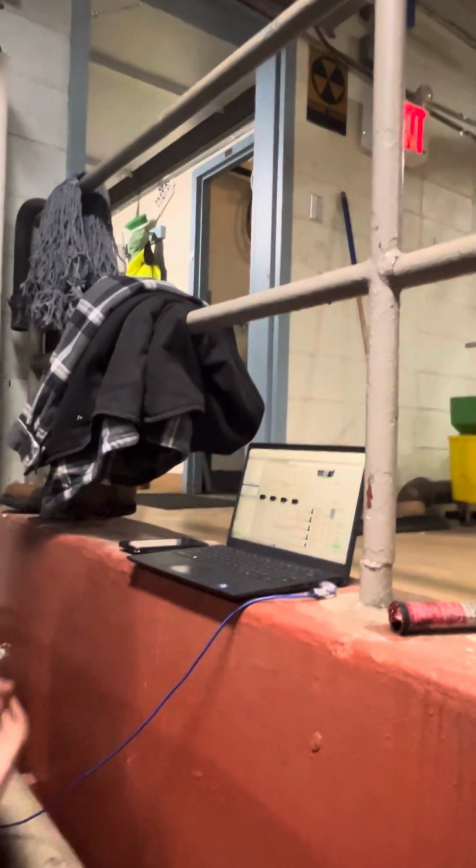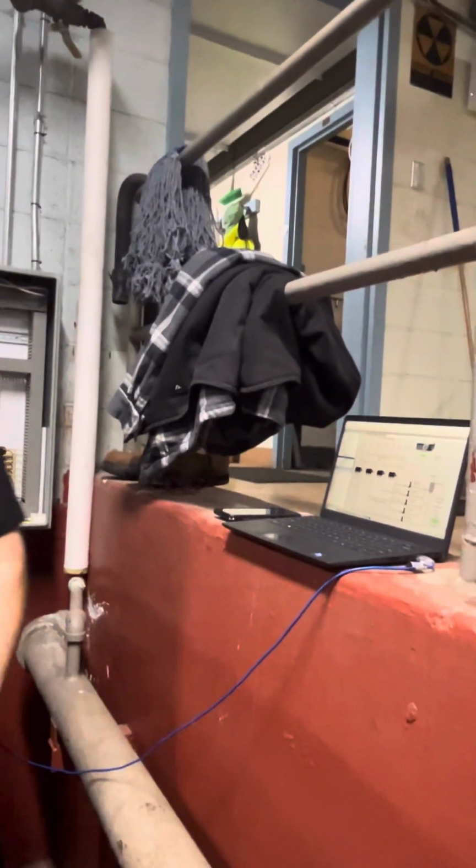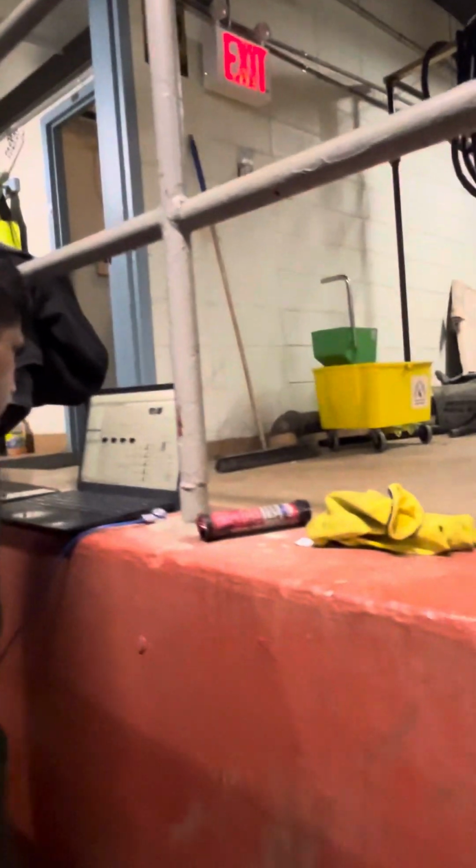Okay. Other than that, there's not much else here. If we were to go flip those on, because we're at 0 pounds and it's definitely been greater than 40 minutes, we're trying to fire all 3 boilers. So we're going to fire all 3 boilers if we go switch all those on right now.